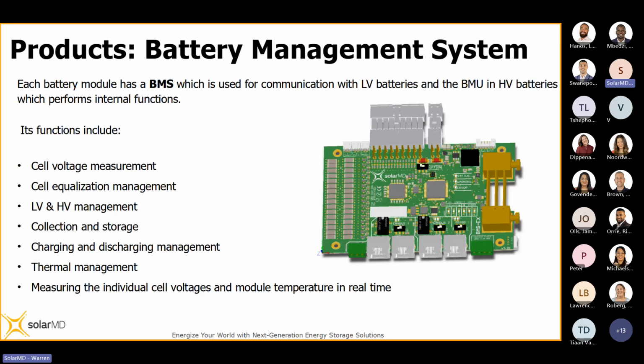Should one of those cells be lower than the other 5, you essentially correct that through the equalization process by overcharging the battery. You overcharge the other 5 cells and bring up the 6th, low cell to the necessary voltage. That's possible with that old school chemistry because the excess energy in the higher cells, now being overcharged, is given off as hydrogen gas. You lose liquid, assuming it's a flooded lead acid battery, but that's not too much of a problem because you can always add that liquid back. If it's an AGM battery, that gas would coalesce and stay within the battery, and things would be fine. So equalization wasn't a technical challenge with old school energy storage solutions like lead acid.